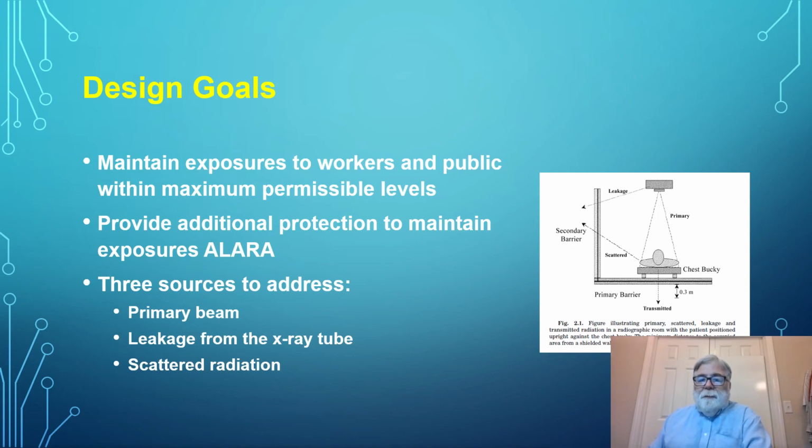In addition, the patient in particular is going to scatter the radiation, and that could pose a hazard to people around. And third, there is a limited amount of leakage that's permissible, and so we need to take that into consideration as we determine what shielding is required.